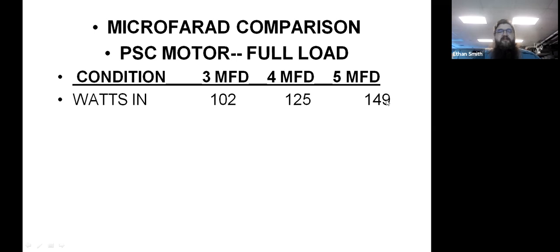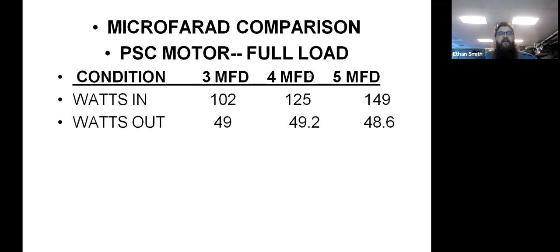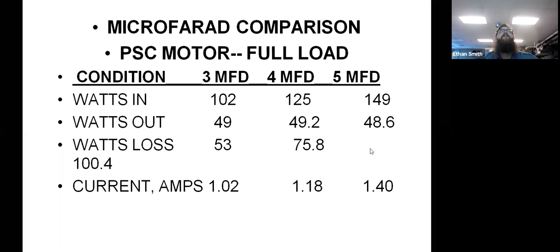Okay, so wattage into the motor steadily climbs as we increase our microfarad rating. Okay, this is the amount of work we get out of the motor. So this is calculated, and we calculate out to about the same. So 49 watts, 49.2, 48.6. That's all within a reasonable margin of error. So that's not terribly significant. We do notice a slight dip on the 5 microfarad, but not conclusive. Okay, so there's our loss. Apparently my 100.4 got moved over for some reason. So we actually lost 100.4 watts in the 5 microfarad and only 75 watts in the 4, and we lost 53 watts.